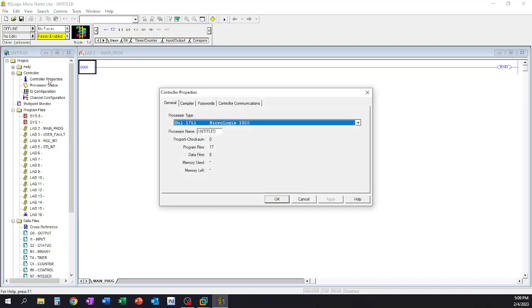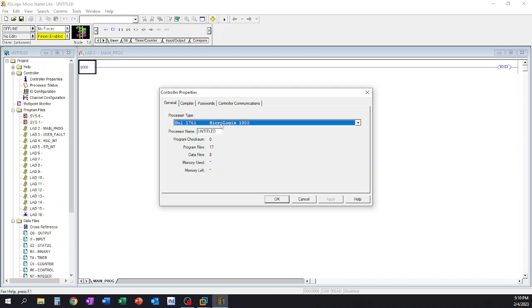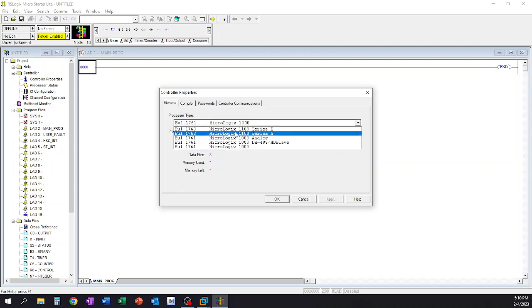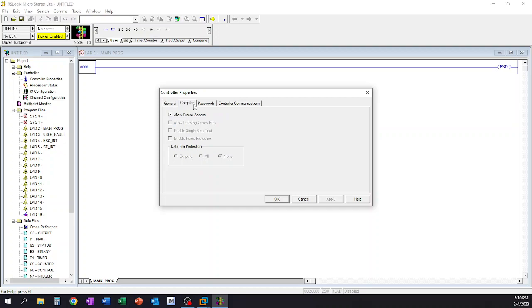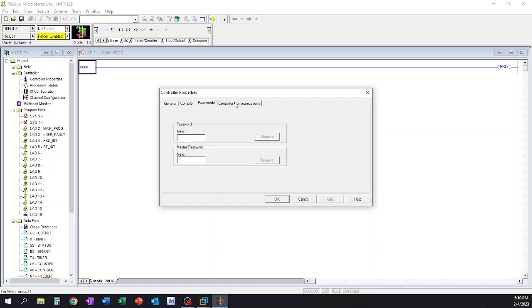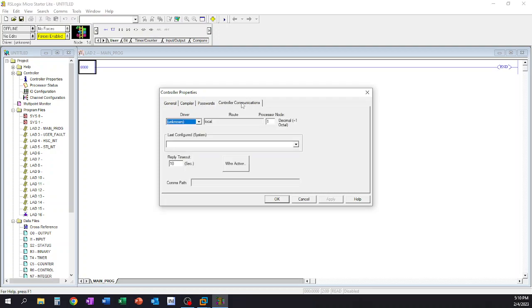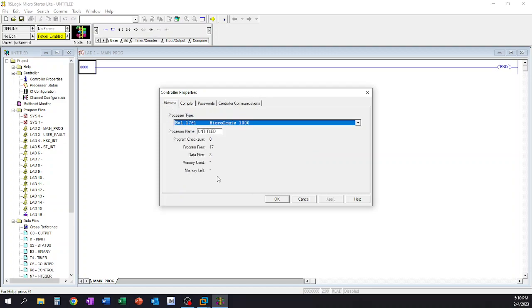If you wanted to change some of that information, you could go into the controller properties tab. Under the controller file folder, you could change the processor name once again. If you needed to change the processor type for any reason, you could change the processor in here. If you wanted to set passwords and lock stuff, you could do that here in the passwords file. If you wanted to set your configurations for some communication, the links, you could do that under the controller communications. In most cases, the only reason why I would use the controller properties is to change the processor type or change the processor name.